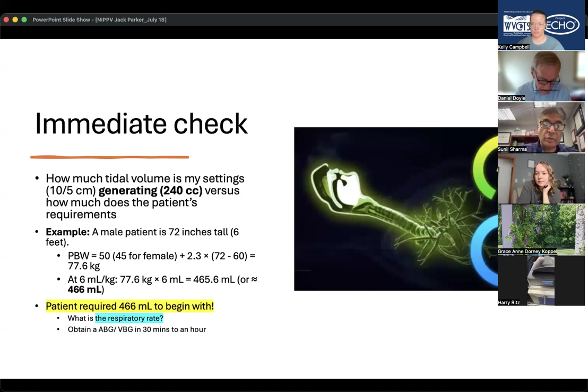The other important physiological fact that we need to remember is that as the respiratory rate goes up, the dead space goes up. In fact, if you're breathing at 30 times a minute, your dead space can be as high as 42 to 45%, which is almost 50% of your lung capacity is now dead space. So all of these have to be taken into account. The higher the breath rate, the respiratory rate, the higher the dead volume, which you have to make sure to compensate for. Next slide, please.